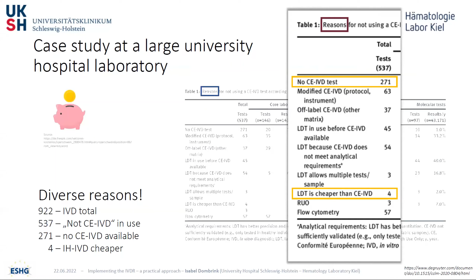And here are listed the reasons why they had to choose a non-CE-IVD. As you can see, for 4 of those 537 assays, the reason is that it's cheaper. Then there are some other reasons, but the most prominent reason is that there's just no CE-IVD test available. It is another fact that in-house devices need to fulfill Article 5.5 of the IVDR and therefore the general safety and performance requirements that are described in Annex I.